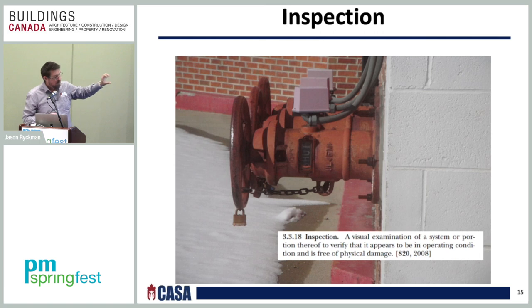So, inspection. A lot of people get things kind of confused when looking at inspection, testing, and maintenance. Sometimes people confuse testing with inspections, inspections with testing, maintenance with testing. Ultimately, that's why you really need to know these definitions. Basically, an inspection is a visual examination of the system or portion thereof to verify that it appears to be in operating condition and is free of physical damage. That's what inspection means in the NFPA 25 document.